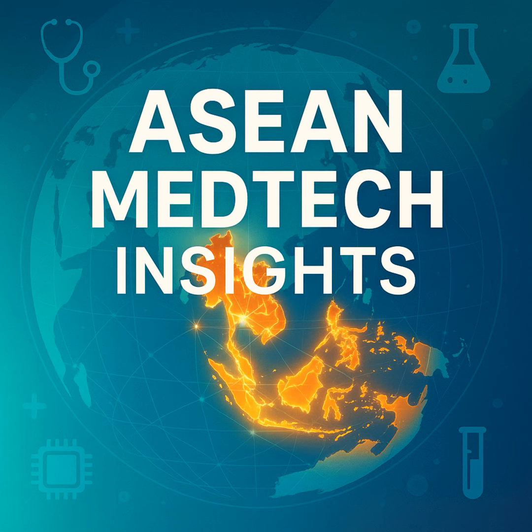Today, we will focus specifically on one of the most critical components of the CSDT, the requirements for clinical evidence. The core purpose of clinical evidence is to scientifically demonstrate the safety and performance of a medical device. According to the ASEAN guidance, this evidence is compiled in a Clinical Evaluation Report, or CER. This is not just a single document, but a comprehensive collection and analysis of clinical data.